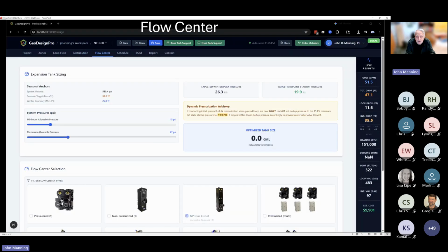I want to talk for a minute about expansion tank sizing. I've seen way too many jobs with enormous expansion tanks on geothermal systems. So what you get to specify is a minimum operating pressure that you want to see in your system, typically to keep the net positive suction head of a pump satisfied. So in this case, we're stipulating 15 psi. The program will automatically tell you what to expect in the winter time, because as temperatures drop, counterintuitively, pressure in the system goes up.